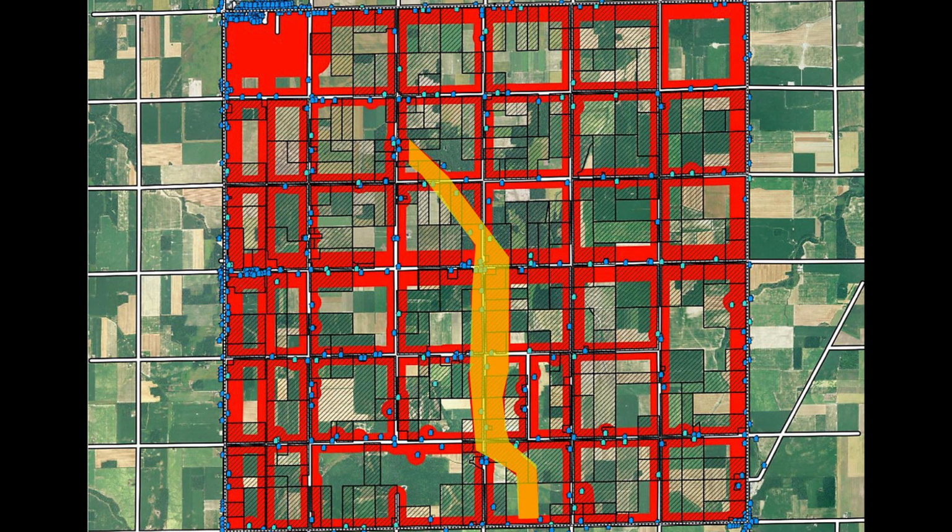We also have overhead utilities. In this case, this is transmission lines, distribution lines, so home service, telephone lines, and other overhead communications. It's mostly communications. And we have a setback again of the total turbine height plus a little bit of margin for these. And I don't believe there's ever been, that I'm aware of, any incidents with public utilities, but the utilities would like the setback, we would prefer the setback, and it's usually not a large impact. On this area I'm showing as an example, there's really one line that cuts through the site, and it's pretty easy to stay back from it and not have any negative impact.